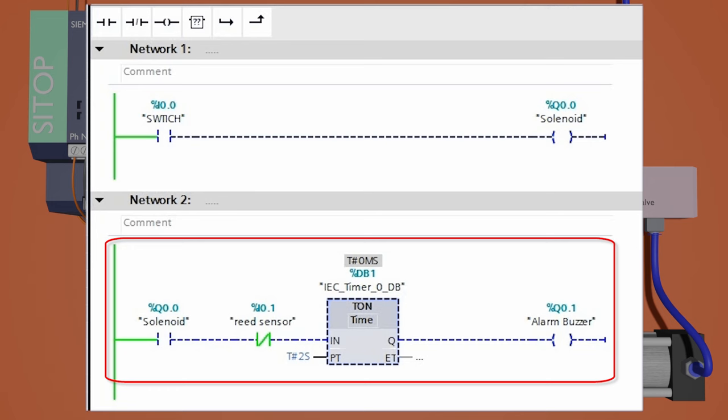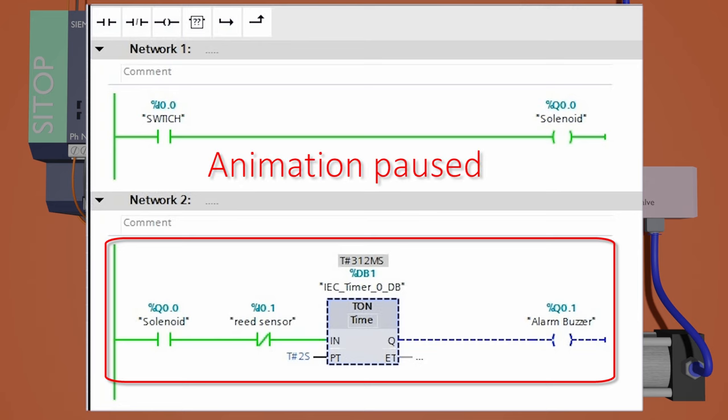Network two is to detect malfunctioning of the cylinder. For example, if we activate the cylinder and the cylinder shaft gets stuck in the middle and cannot extend out fully, and the piston of the cylinder shaft cannot reach the reed switch.